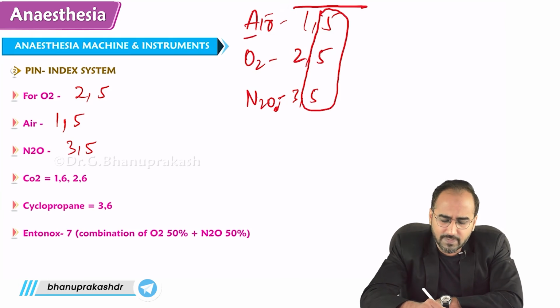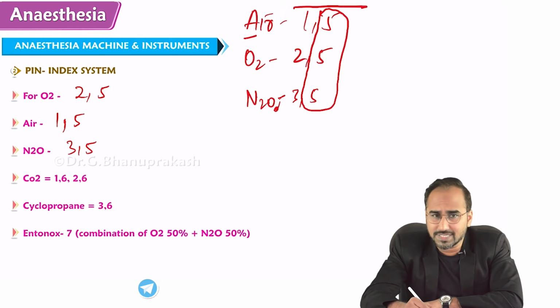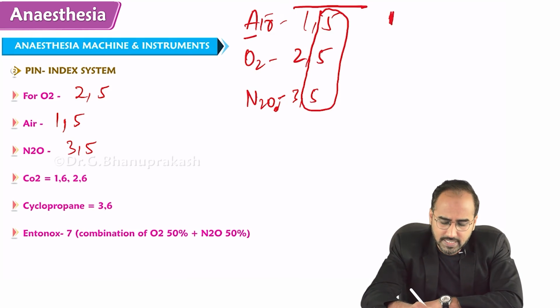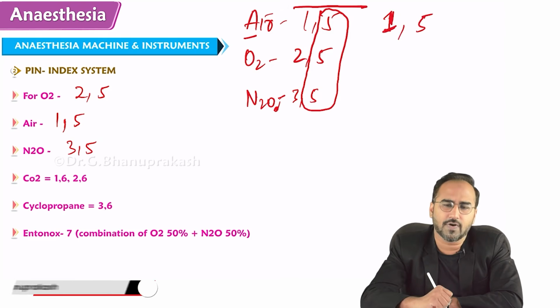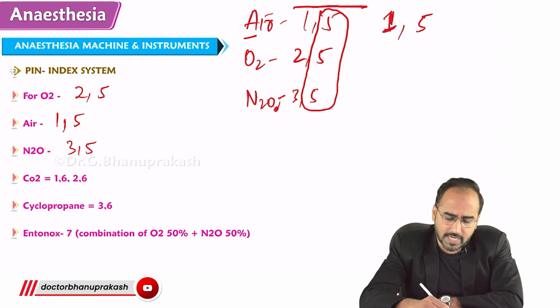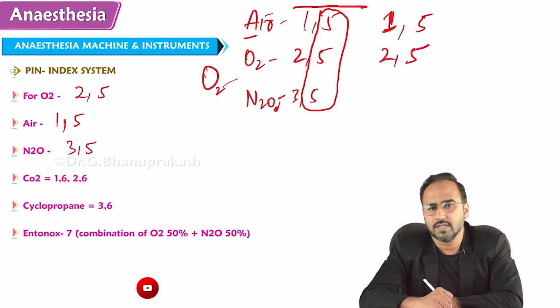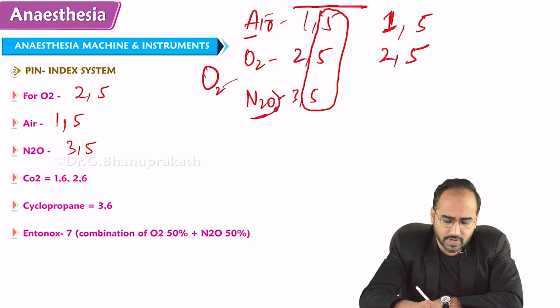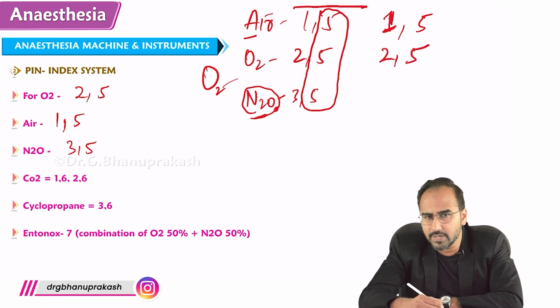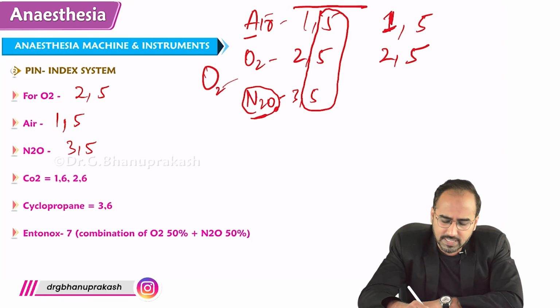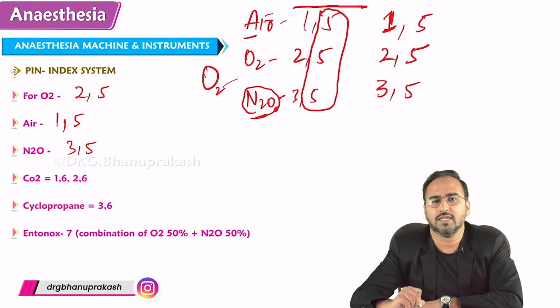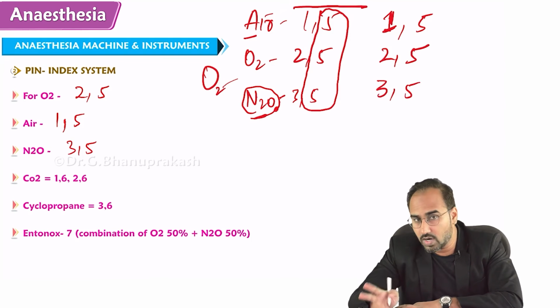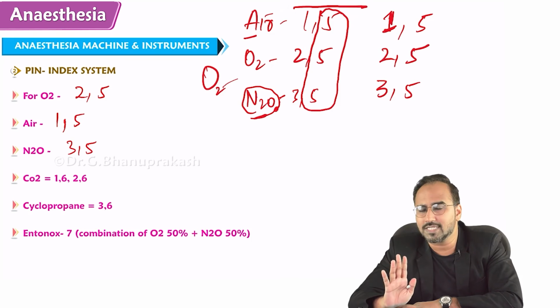Air starts with what alphabet? A. A is the first English alphabet. So the pin index system for air is 1,5. Whenever you are writing oxygen, always write O2. So when you write O2, this 2 comes over here and it becomes 2,5. Whenever you are writing nitrous, what does it mean? Nitrous means 2 molecules of nitrogen and 1 molecule of oxygen. How many molecules? 3 molecules. The pin index system for nitrous is 3,5. Air pin index is 1,5. Oxygen 2,5. Nitrous it is 3,5.